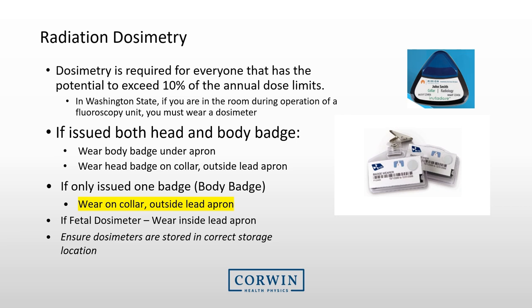If you are issued both a head and a body badge, wear the body badge under the lead apron and the head badge on the collar outside the lead apron. Make sure you identify which badge is which — the head badge will be clearly identified. If you are issued only one badge, such as a body badge, it is worn on the collar outside the lead apron.